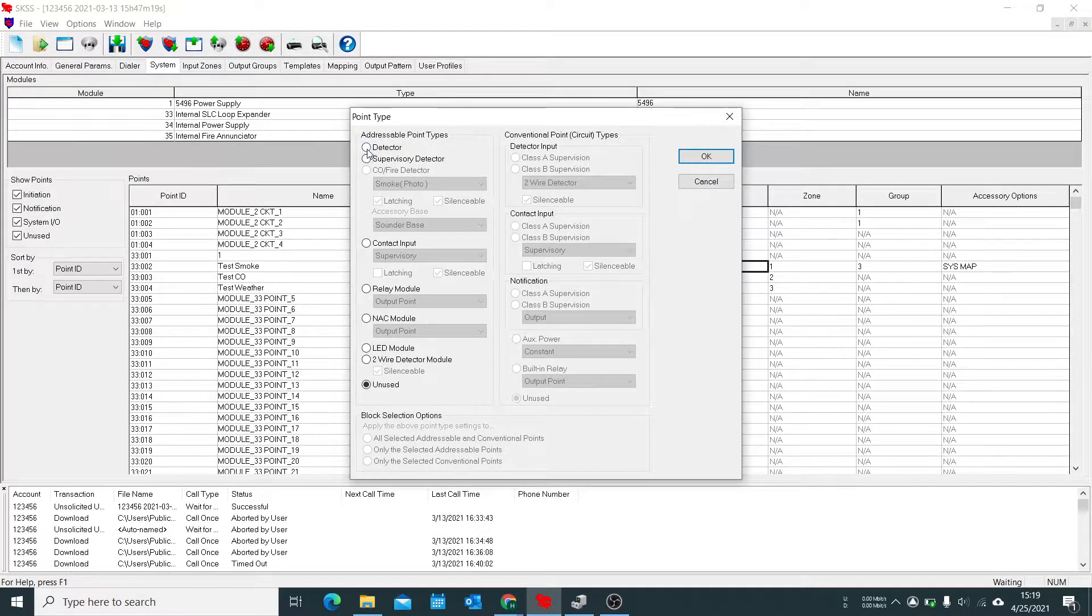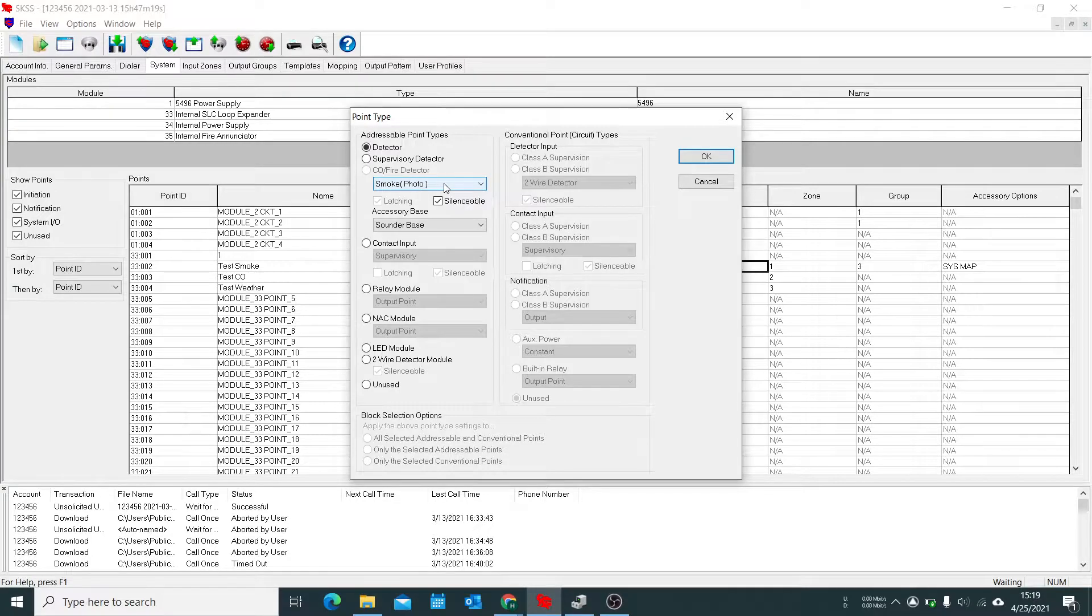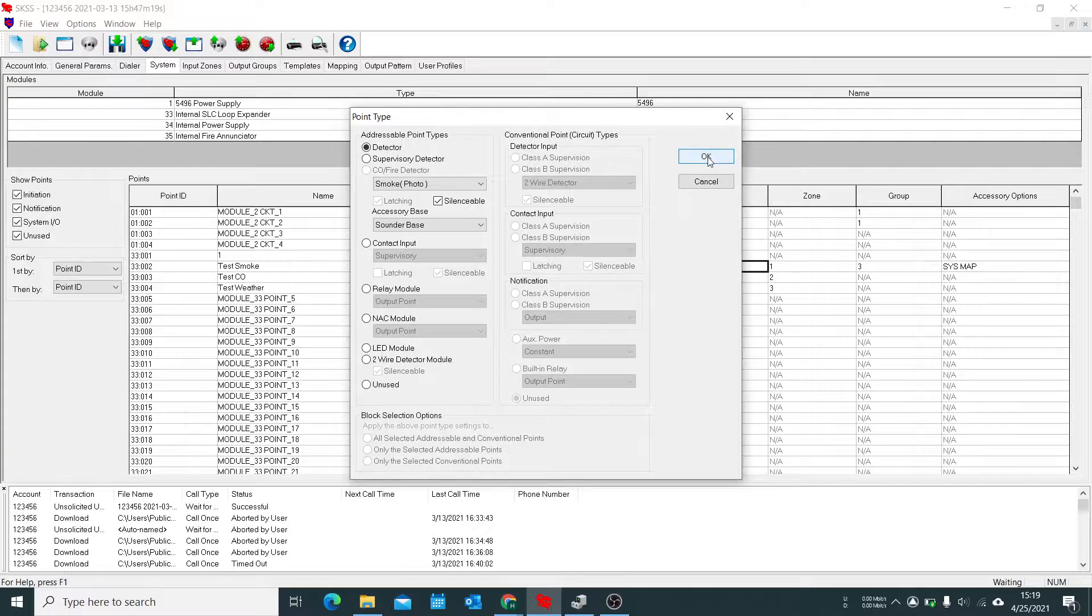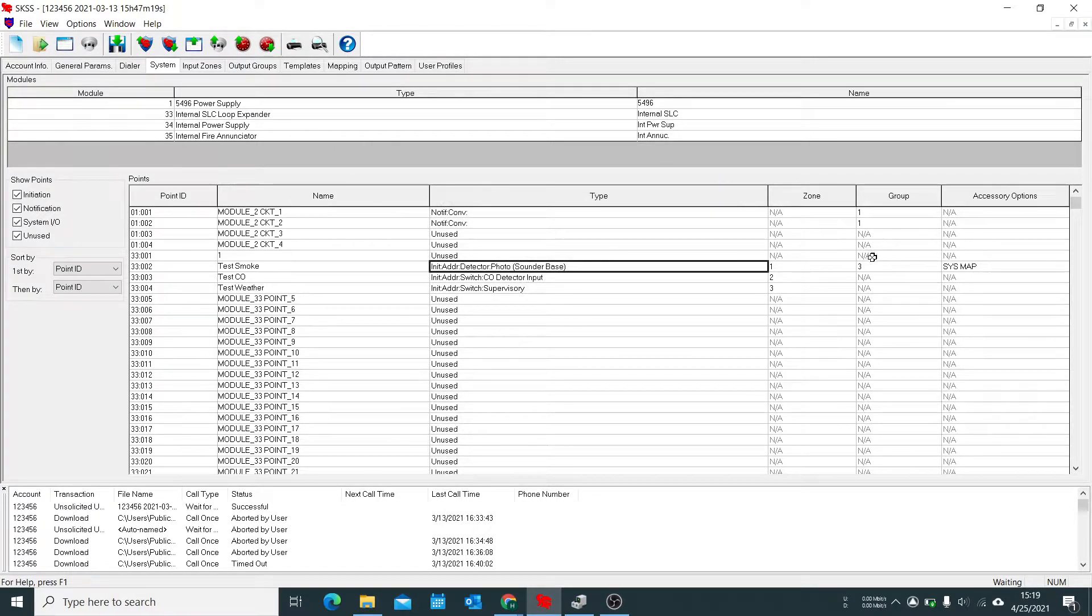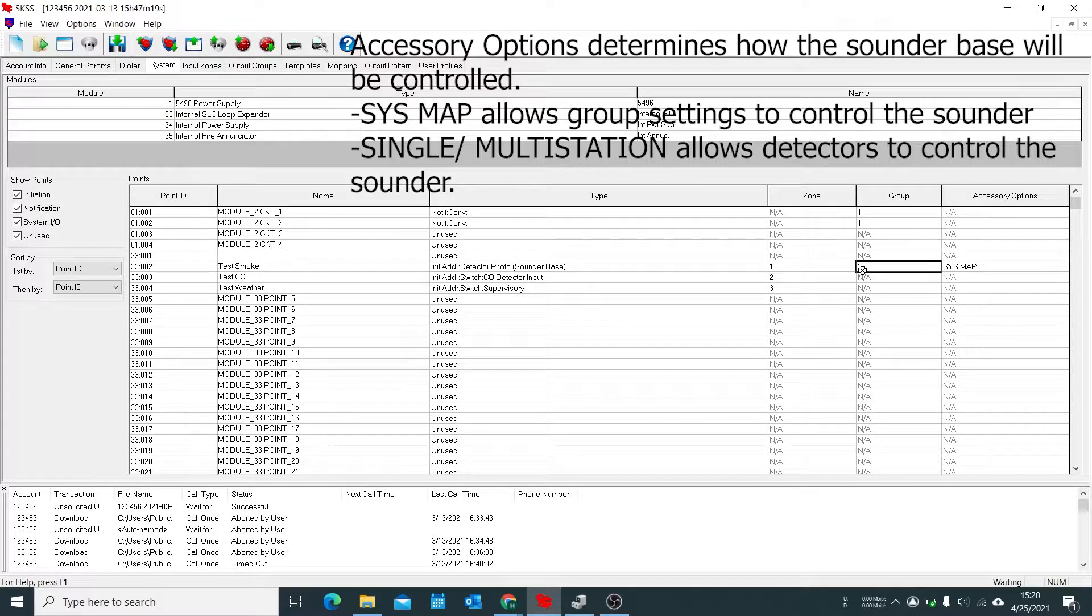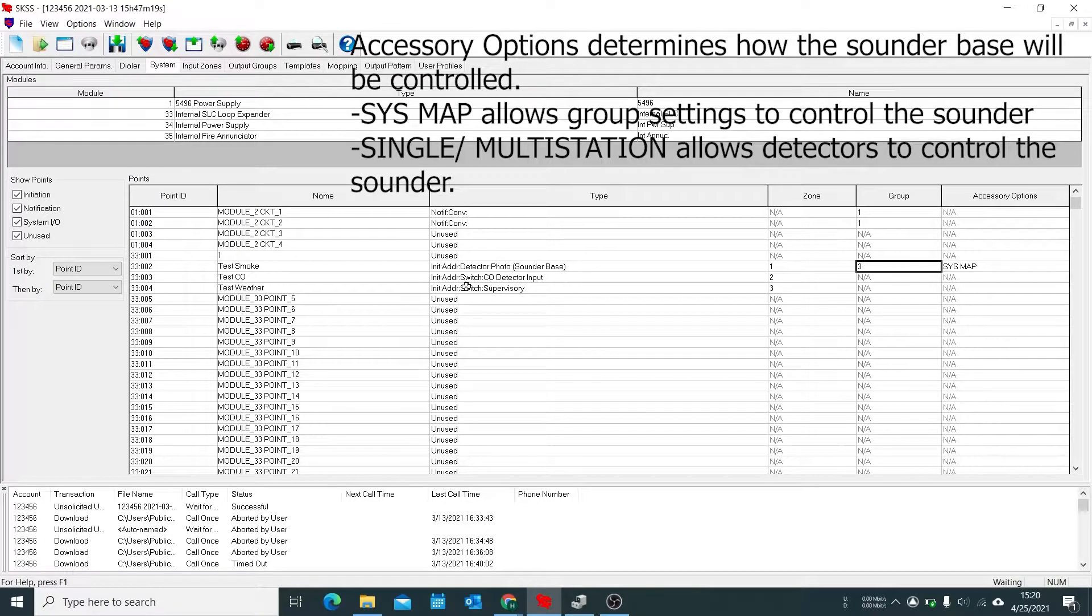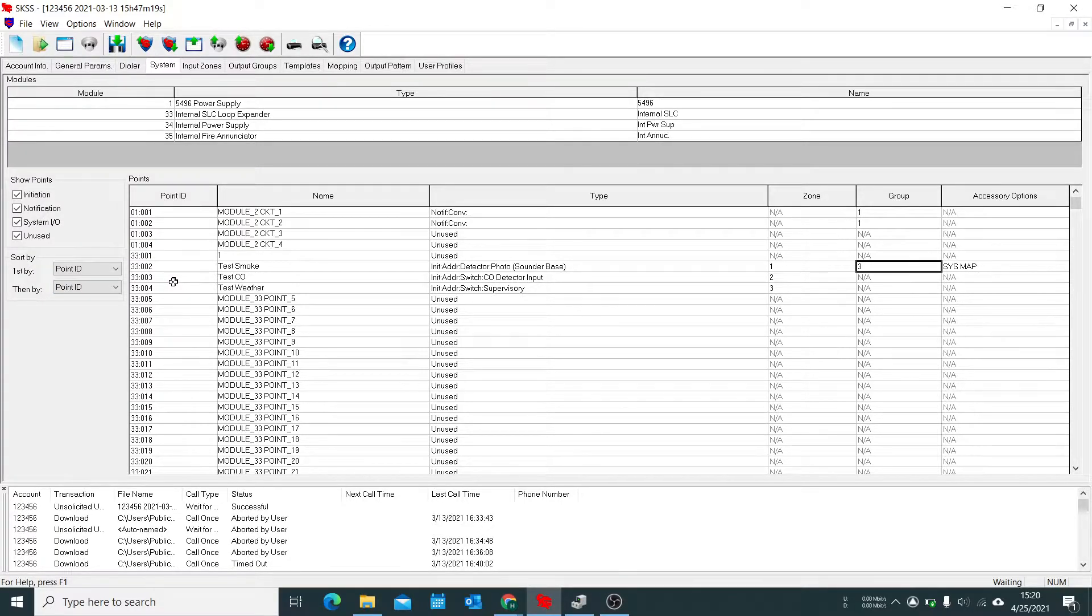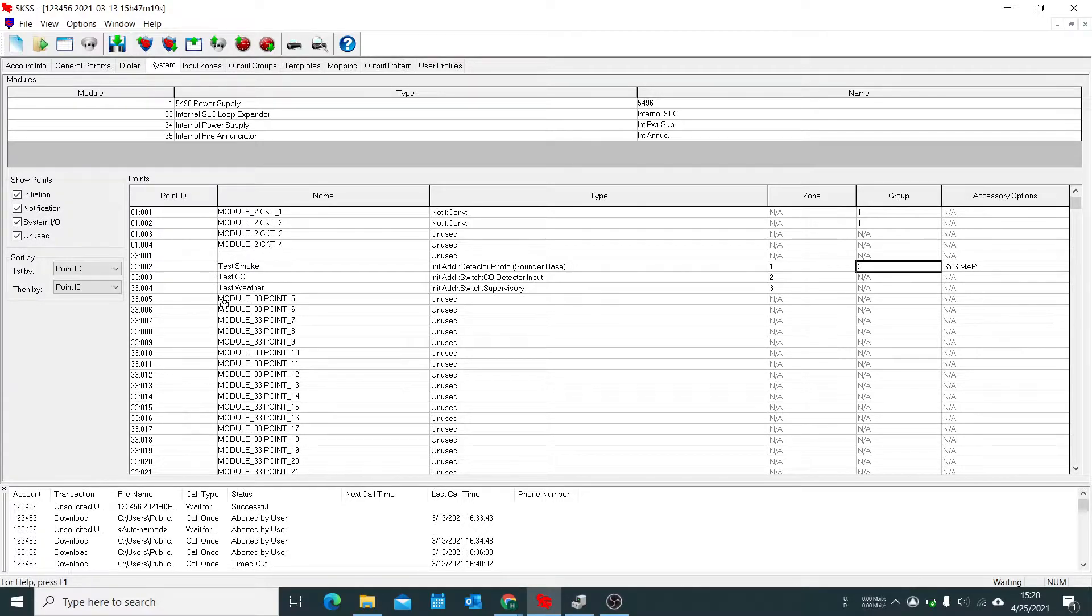Let's say it's unused. I'm going to select detector. It's a photo detector and it has an accessory base which is a sounder base. So when we do that we will get the option for a group. So now that sounder base's output is tied only to this group, in this case group three. And just for reference we have point three tied as a CO detector input and point four as a supervisory.